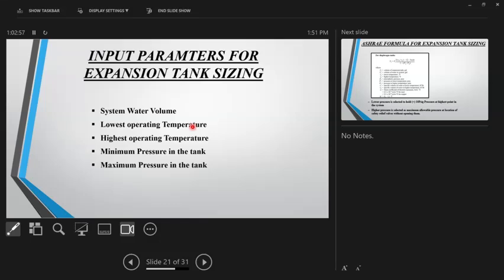The highest operating temperature: if that system is, let's say, closed for a few days, then the water temperature can increase, and at worst it can go to ambient temperature. So the highest operating temperature could be the ambient temperature. Then a minimum pressure in the tank and a maximum pressure in the tank. This we will see in a few slides. So these are the 5 parameters which are actually used to size any expansion tank.